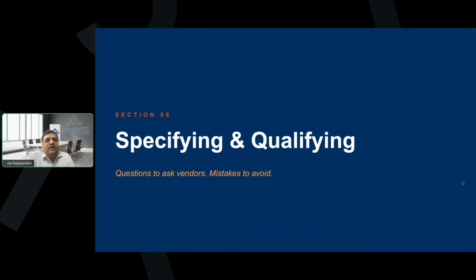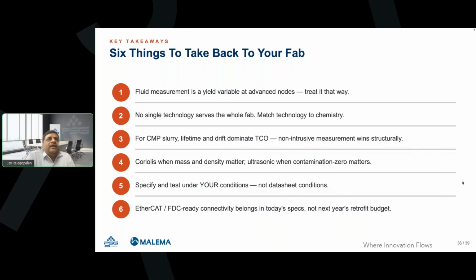So how do you specify and qualify in considering all these criteria? What questions do we need to ask and what mistakes should we avoid? So I listed 6 things which I think are critical takeaways. One is fluid measurement is a yield variable at advanced nodes, and we should treat it that way. It's not just a flow meter costing $500. Is it worth it? But if you've selected a defective technology there, it can lead into even one excursion, as I pointed out earlier in the presentation, one lot of wafer defect can lead into $1 million plus in the cost for finding the root cause and then fixing it.